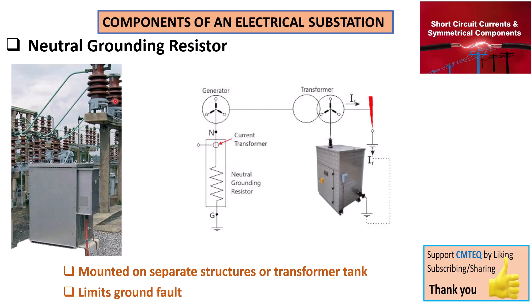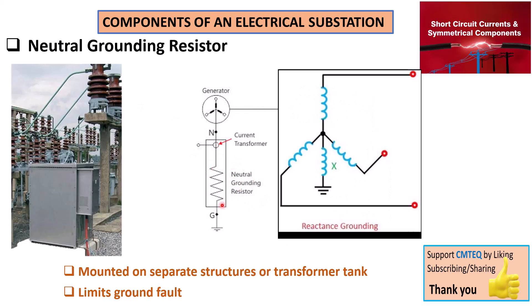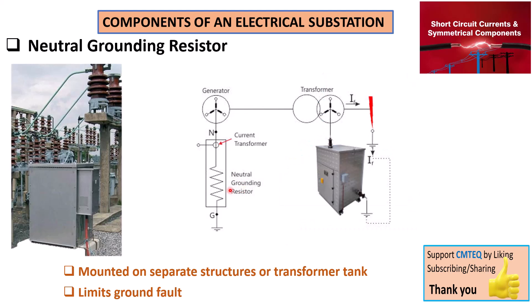The third type of earth grounding is via reactance — we take the resistor away and place a reactance there, which means an inductor, also known as a reactor. Power systems use lots of reactors for fault-limiting capability. Even though you're placing a reactor here to limit the fault current to an acceptable value, you still must allow your current transformer to be able to detect that fault current.